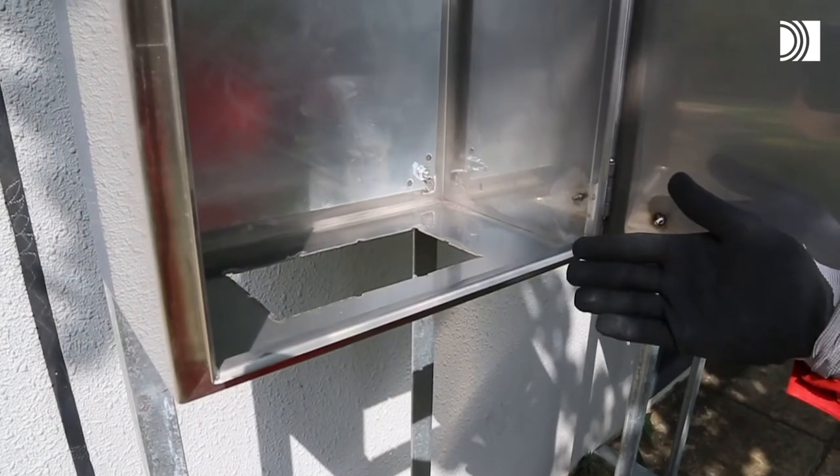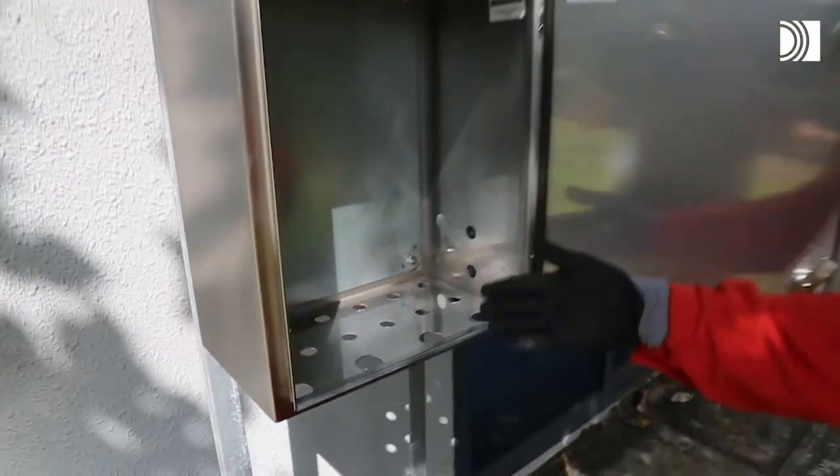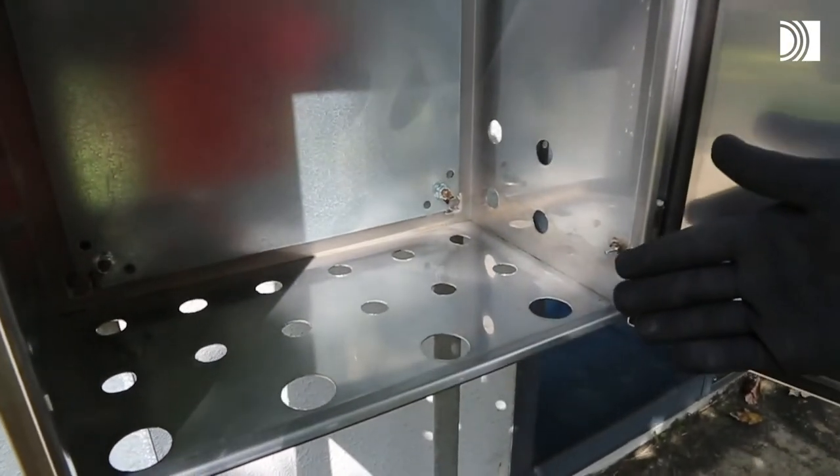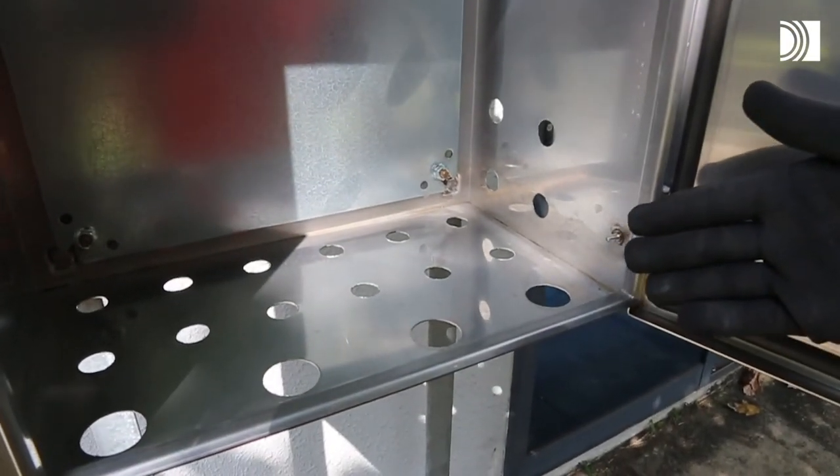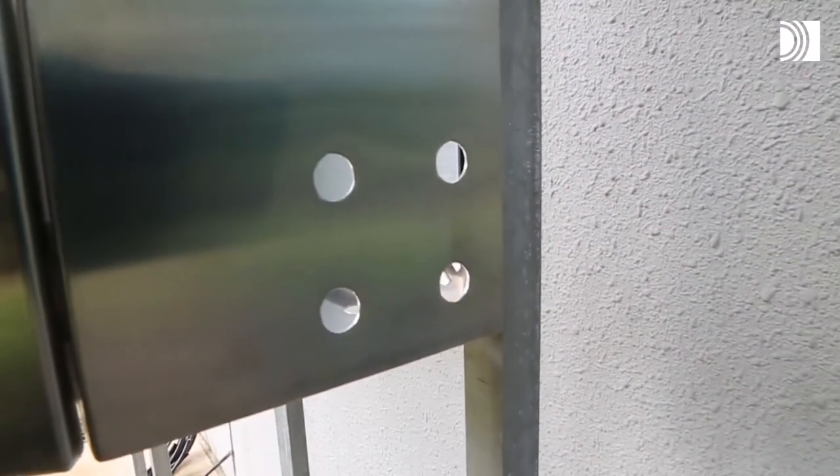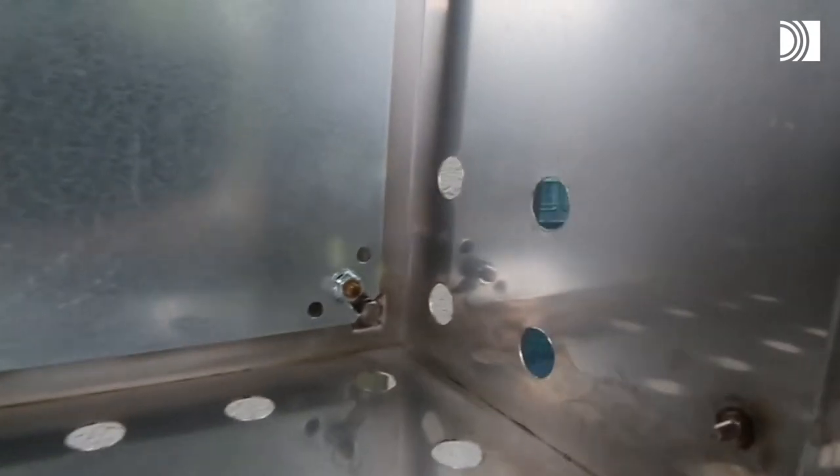Before starting, they made way for 20 cables in the bottom of the enclosure, one opening for Roxtec, and 20 small holes for the cable glands. It took about 30 minutes to prepare the enclosure for Roxtec and about an hour to drill and punch the holes for the cable glands.